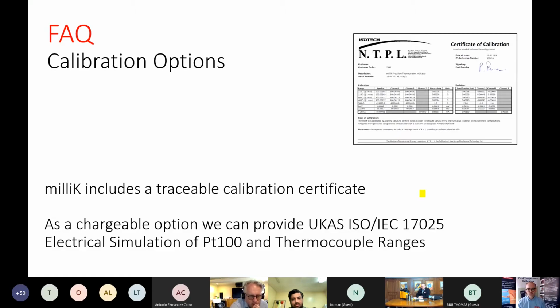So the milliK for the instrument alone includes a traceable calibration certificate. When you buy the milliK with or without a probe, it always includes a traceable certificate, but it's not ISO 17025, because most people don't need that, but some will. So it's a chargeable option. If you want ISO 17025 for the electrical simulation, where we inject ohms and voltages to calibrate the PT100 and thermocouple ranges, then that's an additional cost.